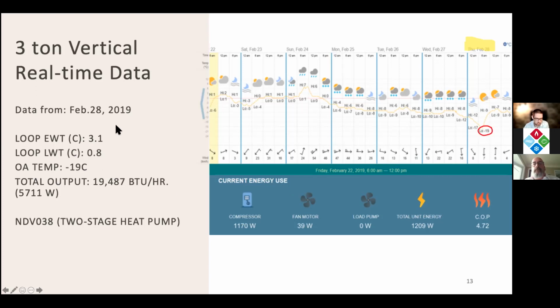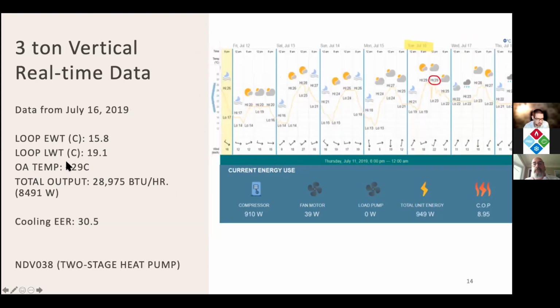Now, if we fast forward to the summertime, to see what's going on in cooling. We've gone through the winter, and now we've probably done a little bit of cooling since May. So our loop temperature is again back up to 15 degrees Celsius. We've got a decent temperature difference there. And I think this was probably one of the warmer days of the year, 29 degrees Celsius. And the important number here is the EER is 30.5, which is pretty incredible.